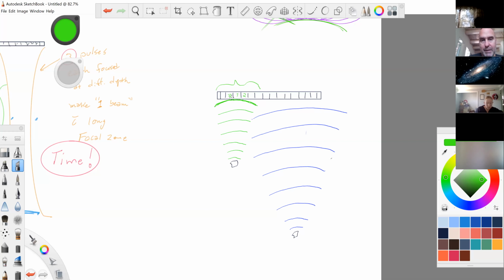These two are going to be just slightly behind this one, then 3, 3, 4, and 4. So remember, this is the opposite. This is coming back up, but there is a curvature of the echo simply created by the fact that it's spreading out. Those individual elements are going to hear that echo at very, very small interval differences, maybe microsecond differences, but they're still going to hear them differently.